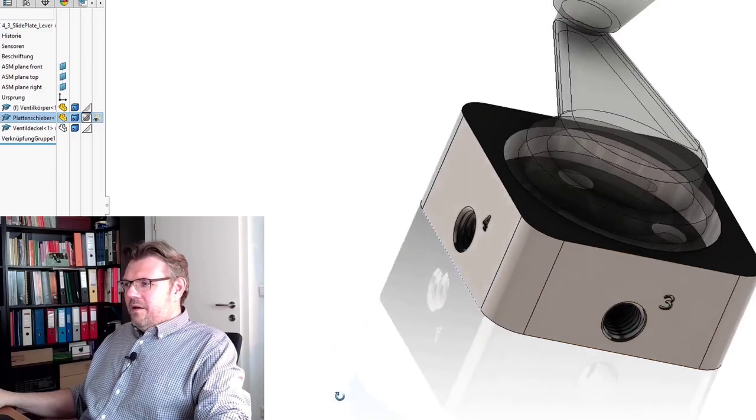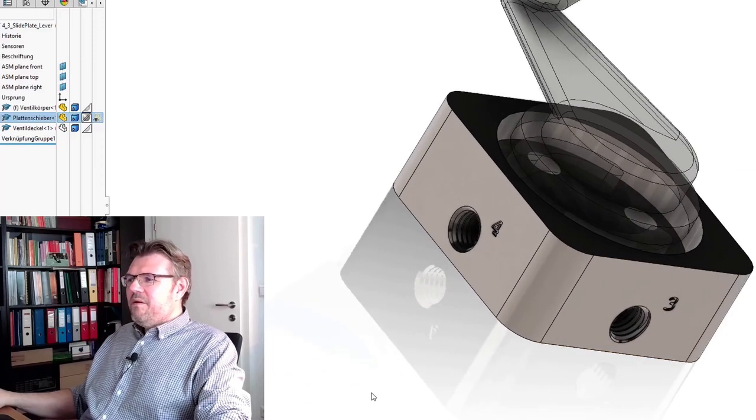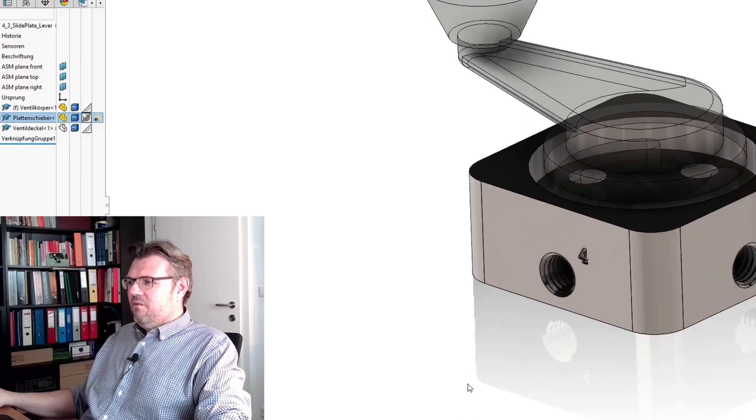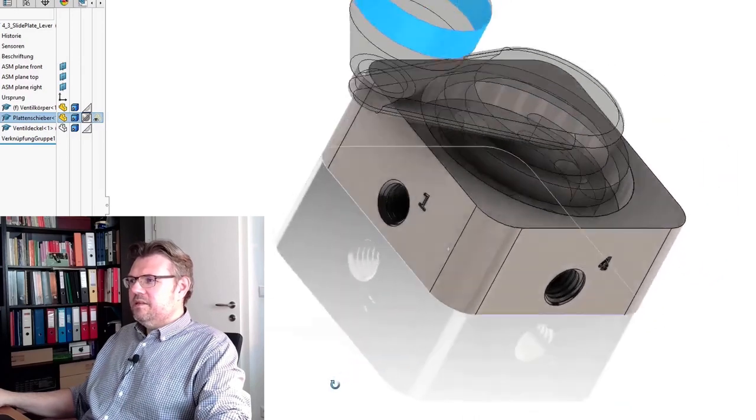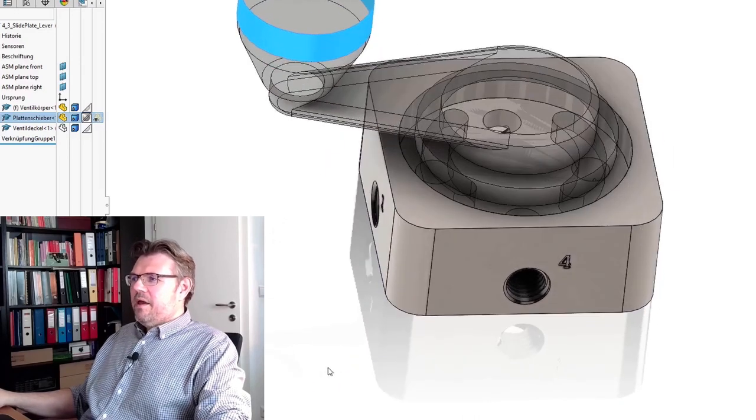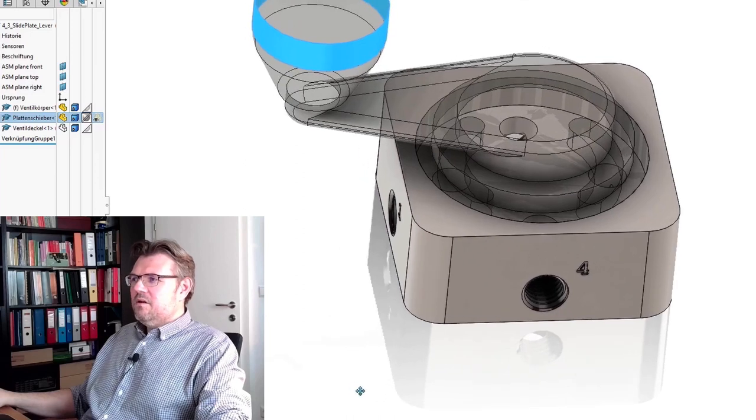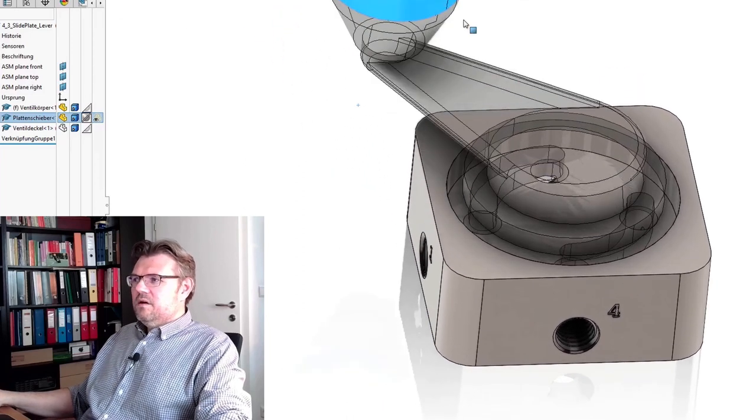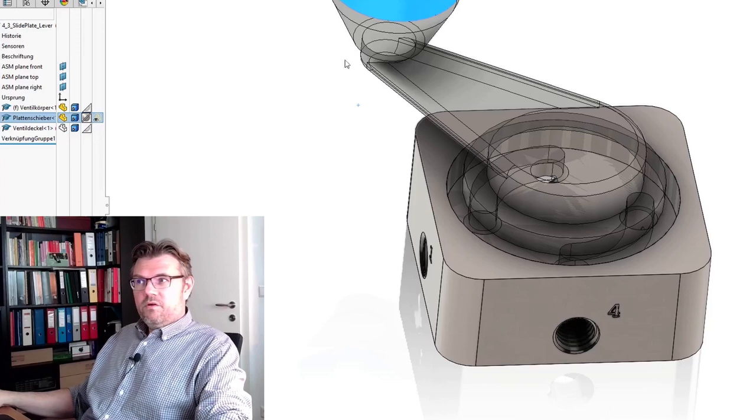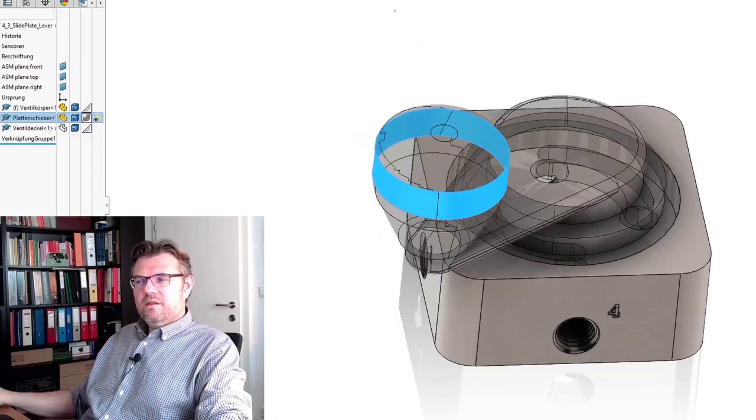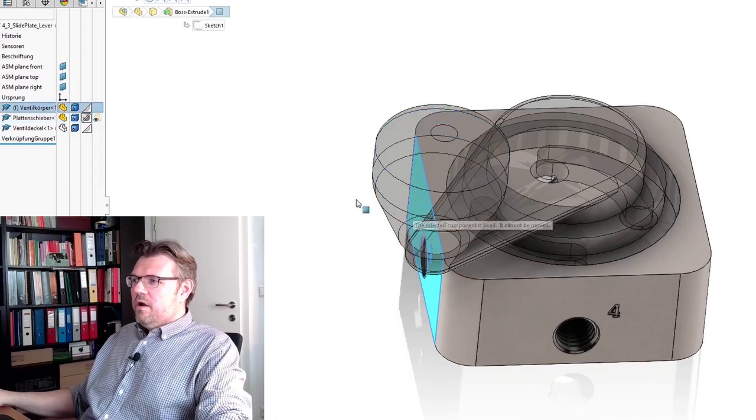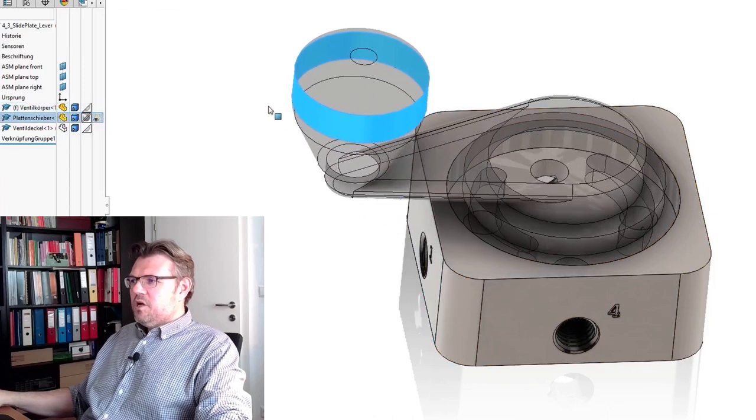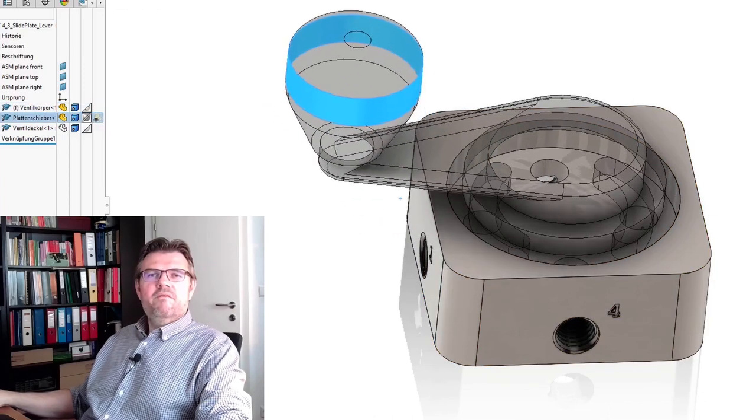So what does it mean? If I'm using exactly this valve here by connecting a double-acting cylinder, I could either move it in one direction, I could move it in the other direction, or in middle position, I'm just stopping it wherever it goes.